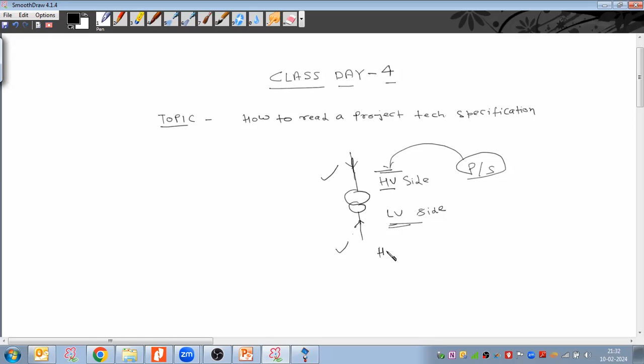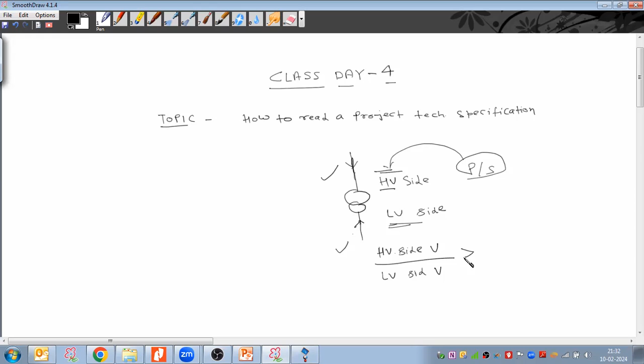Now coming to the topic: in a transformer, when the ratio of HV side voltage to LV side voltage is greater than 2, for example a transformer which is 220 by 33 kV, dividing 220 by 33 gives a result greater than 2, in that case it is preferred to use a two-winding type power transformer.